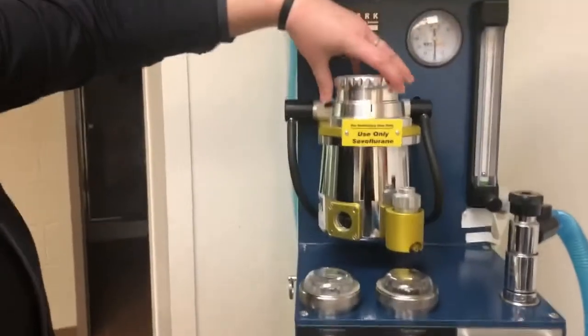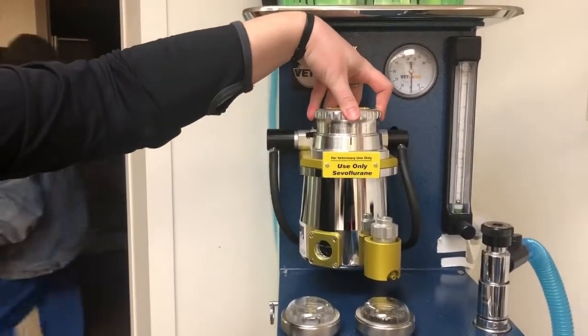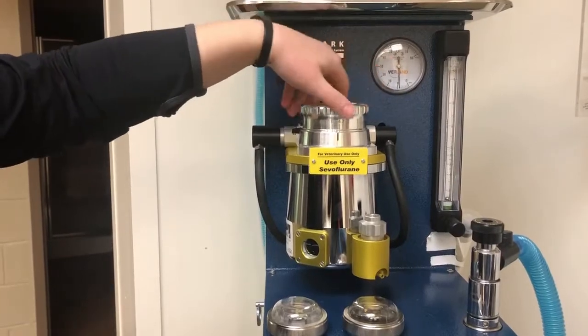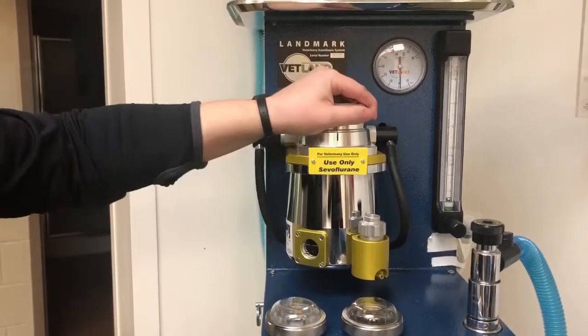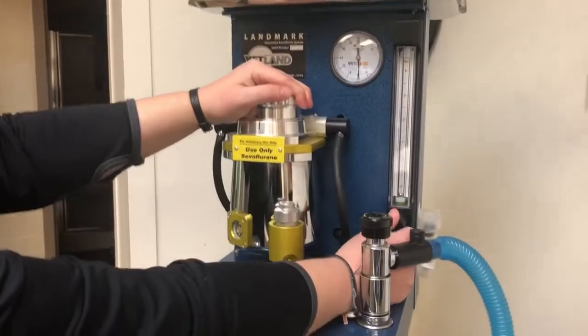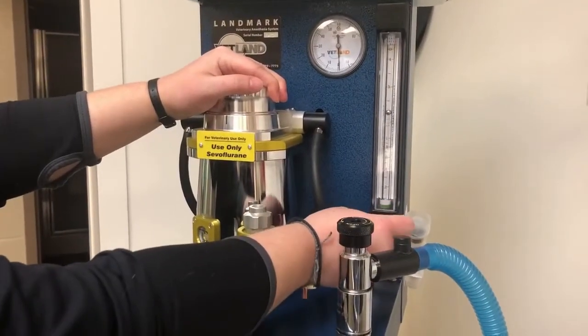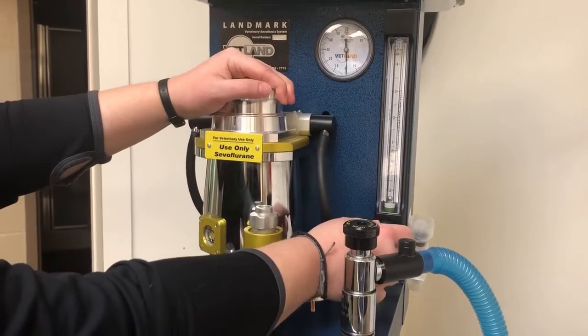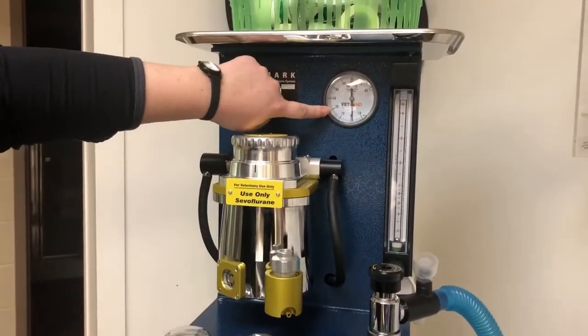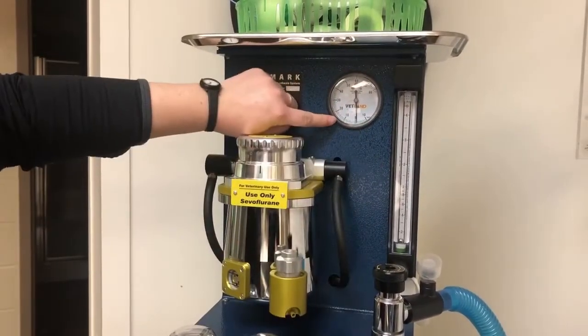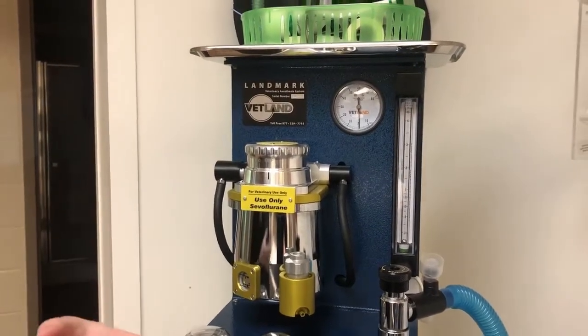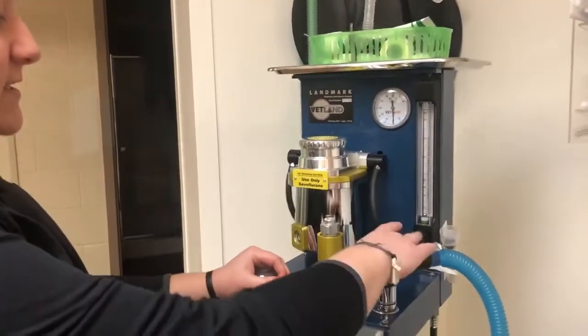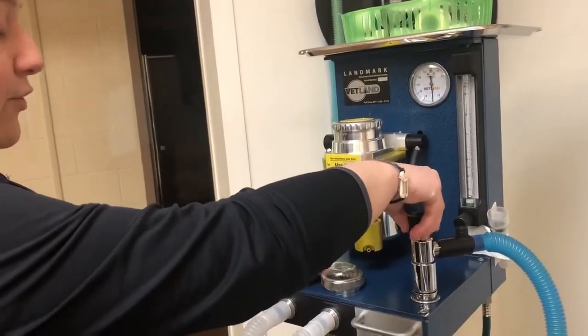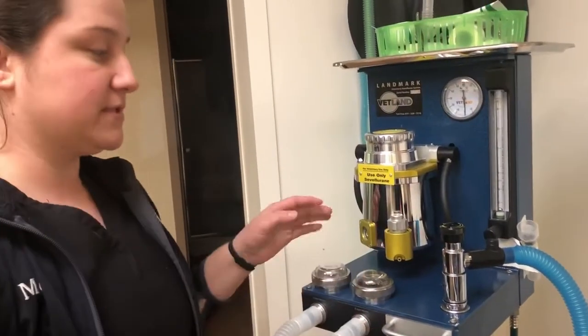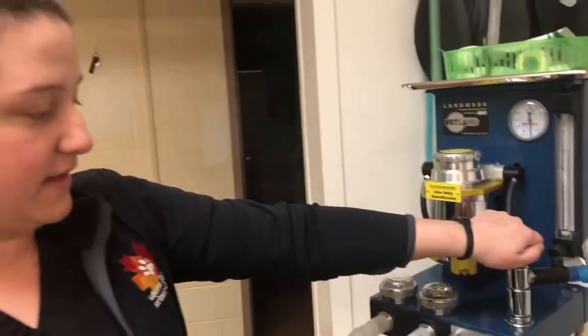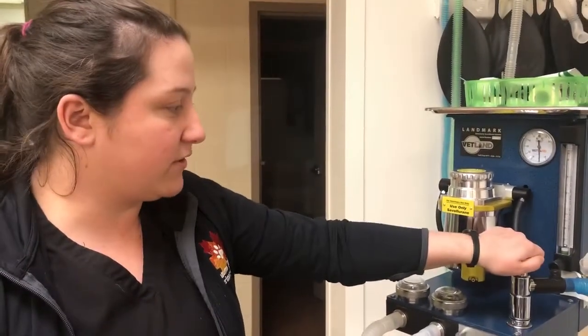and if you need to add more. Generally, maintenance for sevo is around 3 to 4, so it's a little bit higher than we run isoflurane. This is my oxygen flow meter, so you can monitor my oxygen rate. The manometer here keeps track of the pressure. You never want that pressure to exceed 20 when you're giving manual breaths or anything like that. This is my pop-off valve. You want to make sure that's always open anytime you are actually using this on a patient, because if it's closed, then the animal can't exhale and it can cause damage to their lungs.